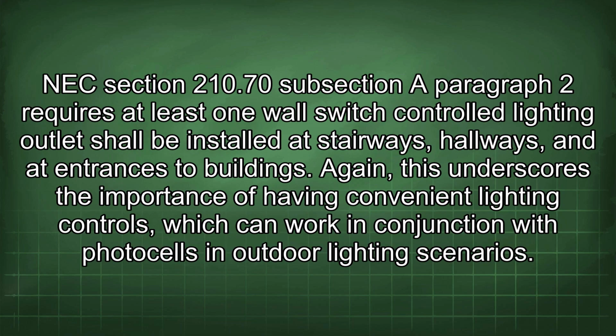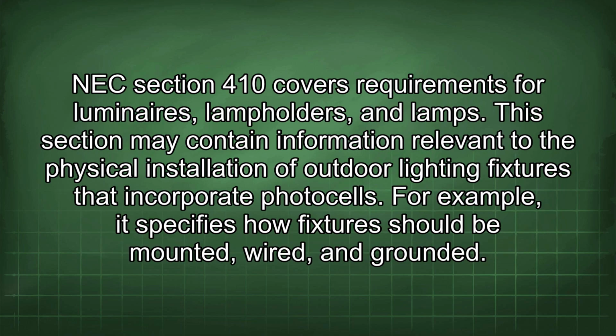NEC section 210.70 subsection A paragraph 2 requires at least one wall switch controlled lighting outlet shall be installed at stairways, hallways, and at entrances to buildings. Again, this underscores the importance of having convenient lighting controls, which can work in conjunction with photocells in outdoor lighting scenarios. NEC section 410 covers requirements for luminaires, lamp holders, and lamps. This section may contain information relevant to the physical installation of outdoor lighting fixtures that incorporate photocells. For example, it specifies how fixtures should be mounted, wired, and grounded.